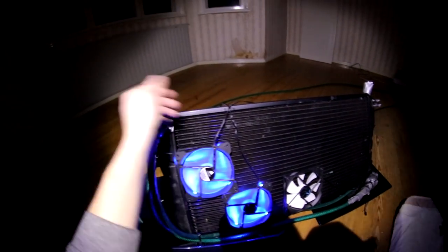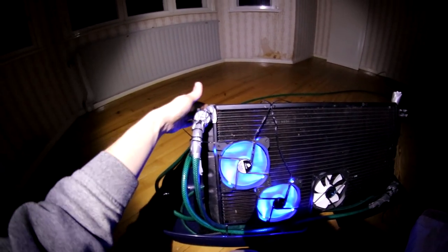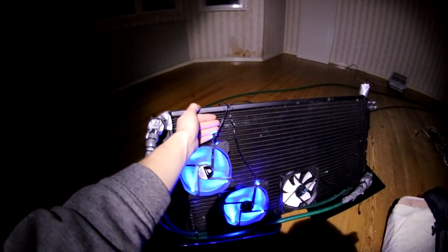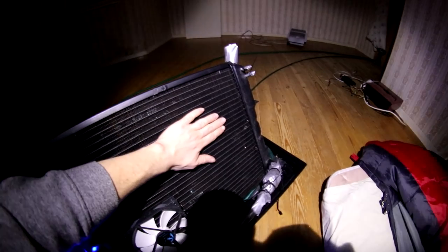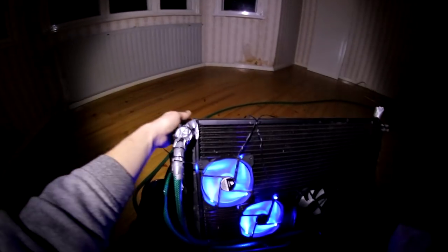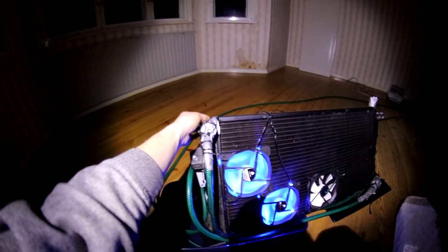Here is the radiator. There's very little temperature drop across the lines — less than 1C — so this is going at 36 to 37C. It's warm to the touch. My thermocouple downstairs is probably a bit off. The intakes are definitely warm and the outlet is still pretty much warm as well — definitely over body temperature, it feels like.